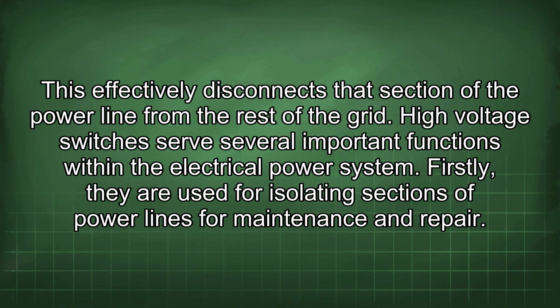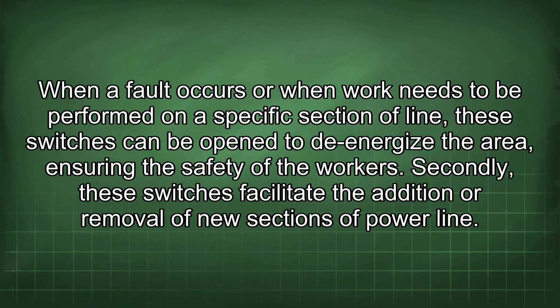High voltage switches serve several important functions within the electrical power system. Firstly, they are used for isolating sections of power lines for maintenance and repair. When a fault occurs or when work needs to be performed on a specific section of line, these switches can be opened to de-energize the area, ensuring the safety of the workers.